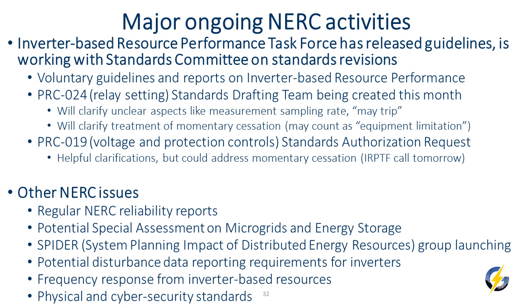The first is PRC-24, which covers the relay and protective controls that protect all generators. In inverters, these are used so that if voltage or frequency goes out of certain bounds, the plant will disconnect to protect itself and the system. That was the primary issue we saw, where a large amount of PV generation dropped out. So there's an effort to clarify many aspects of that PRC-24 standard regarding what's expected of inverters and how they treat these disturbances and ride through them.